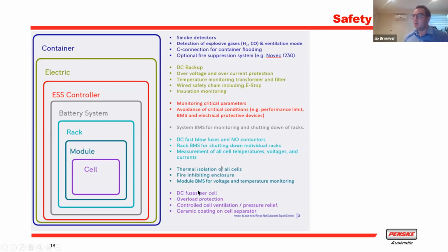On top of that, on a module level, each module is thermally isolated, with a battery management system that makes sure all the voltage and temperature stay within the allowable bandwidth, or otherwise isolates that particular module. On a rack level, we have similar management systems in place - I won't go through all of them, it might be a bit boring.